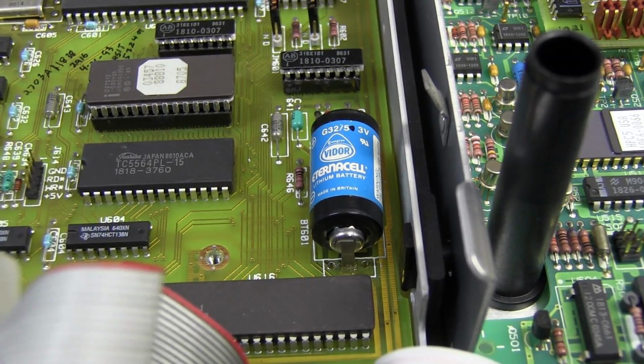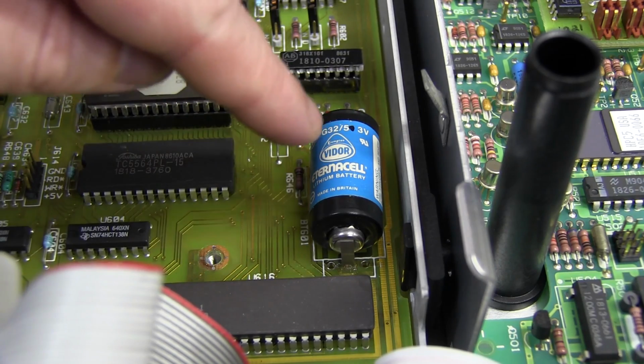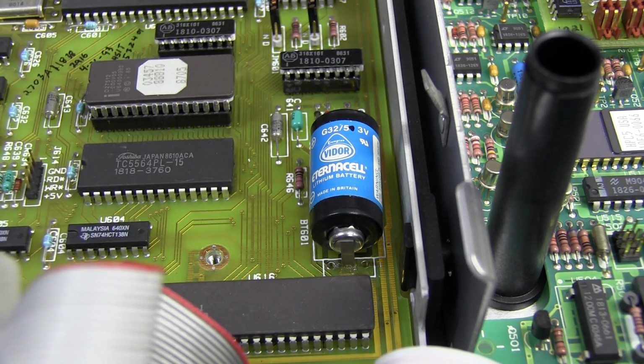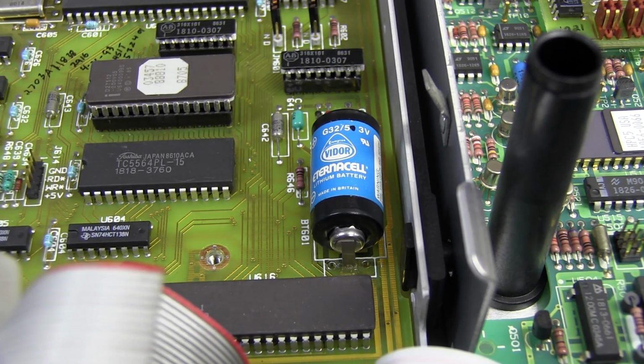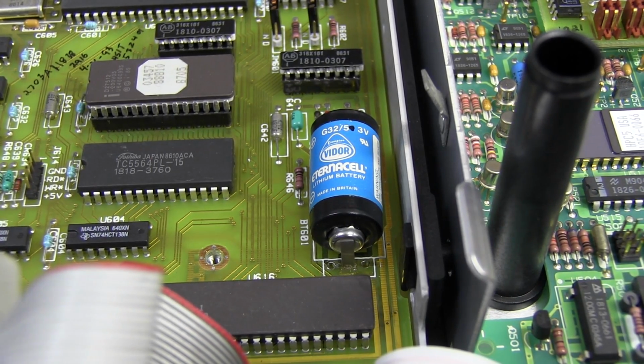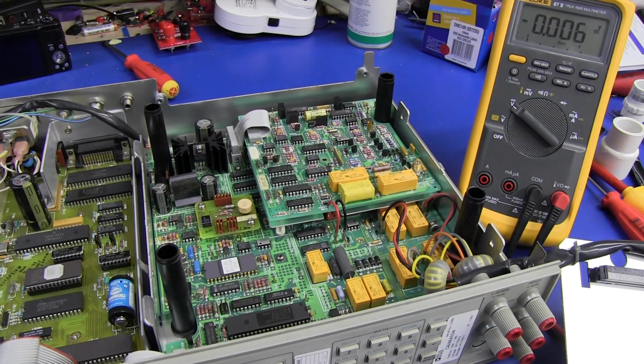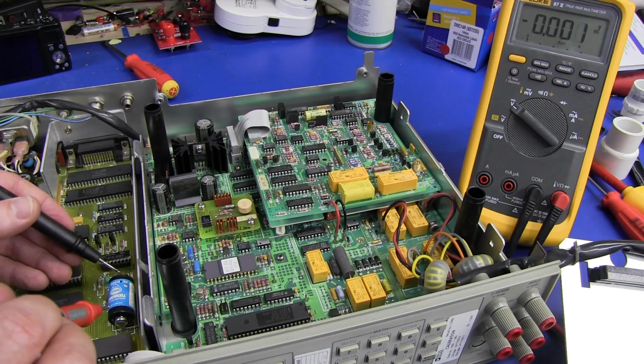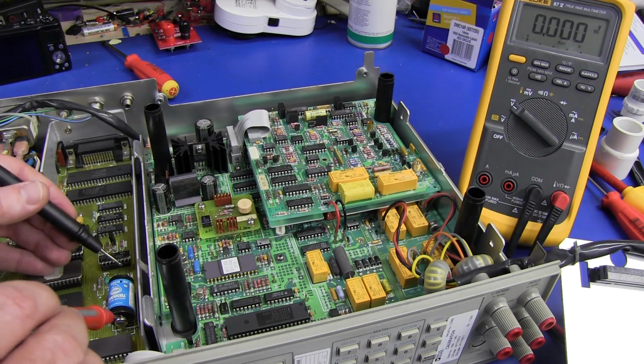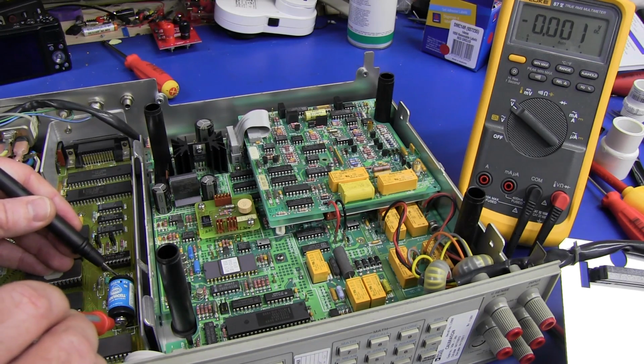You have to be very careful, by the way, when you're opening these things, servicing them, prodding and poking around in these things. Don't short out that battery at all, and don't replace it with the power off, because you will lose all your calibration data in this thing. So I'm going to check the voltage on this, make sure it's still good. Now, make sure I don't have my meter set to amps, because that would be really embarrassing. I'd short out my battery and I'd lose all the fantastic calibration and the bang-oniness, if that's a term, I'm going to invent it, of this thing.